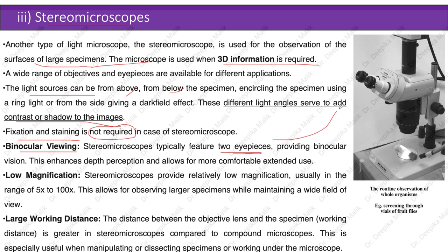Stereo microscopes typically feature two eyepieces providing binocular vision, which enhances depth perception and allows for comfortable extended use. They provide relatively low magnification, usually in the range of 5x to 100x, allowing for observing larger specimens while maintaining a wide field of view. The working distance — the distance between the objective lens and the specimen — is greater in stereo microscopes compared to compound microscopes, which is especially useful when manipulating or dissecting specimens.